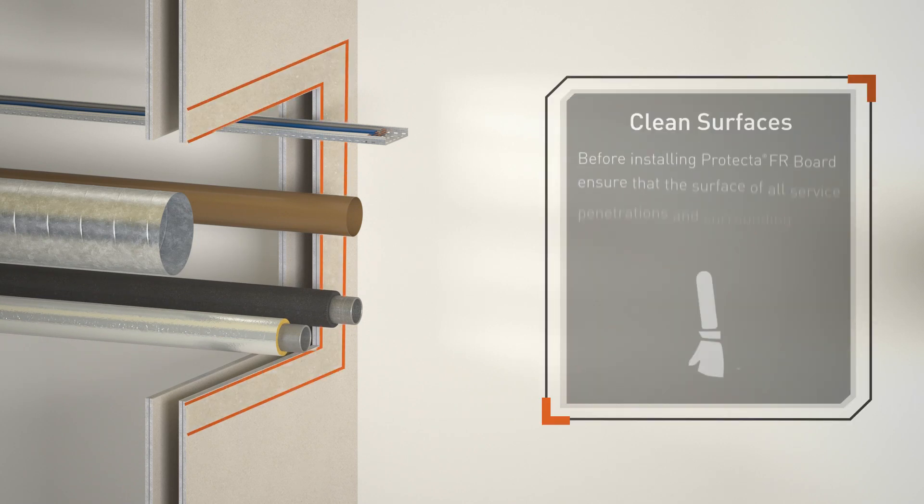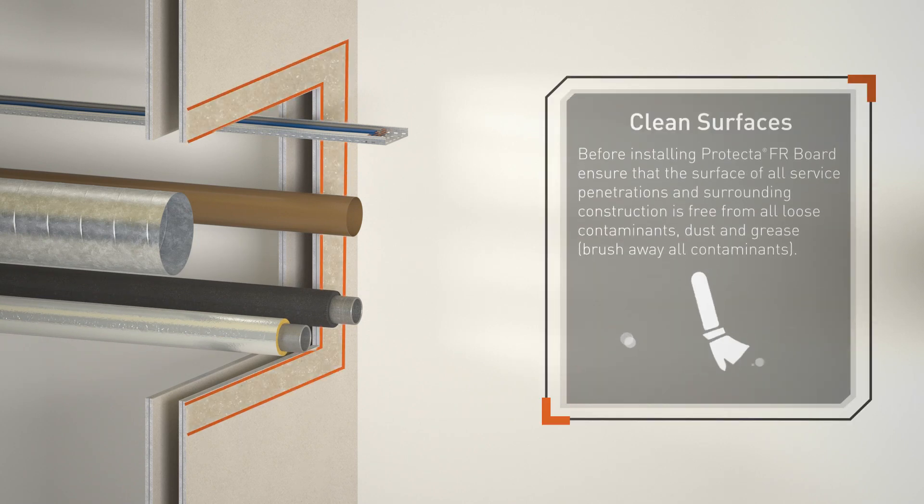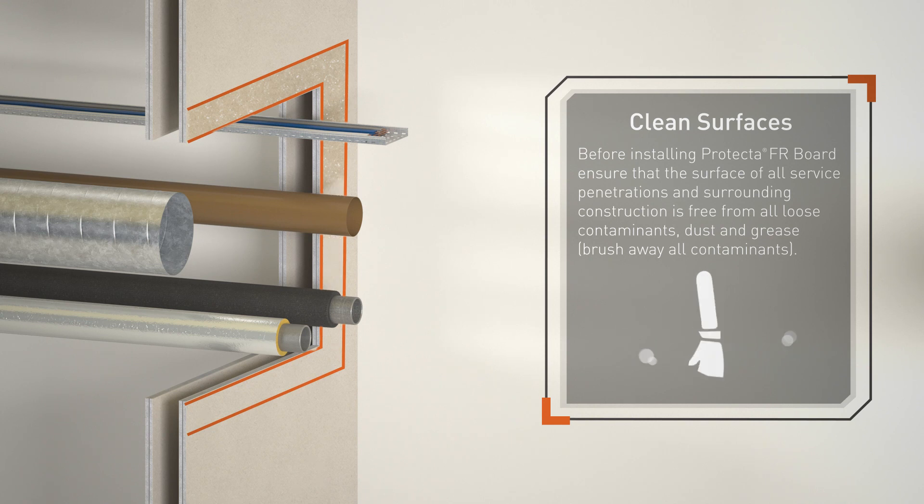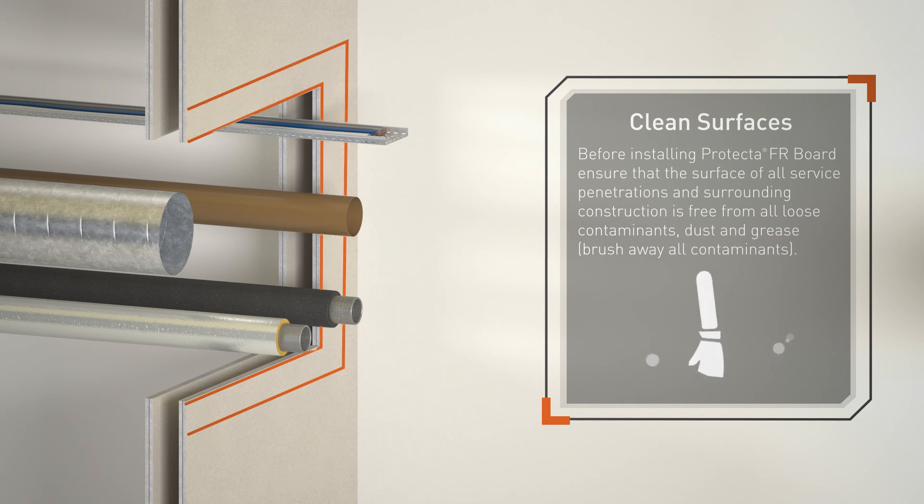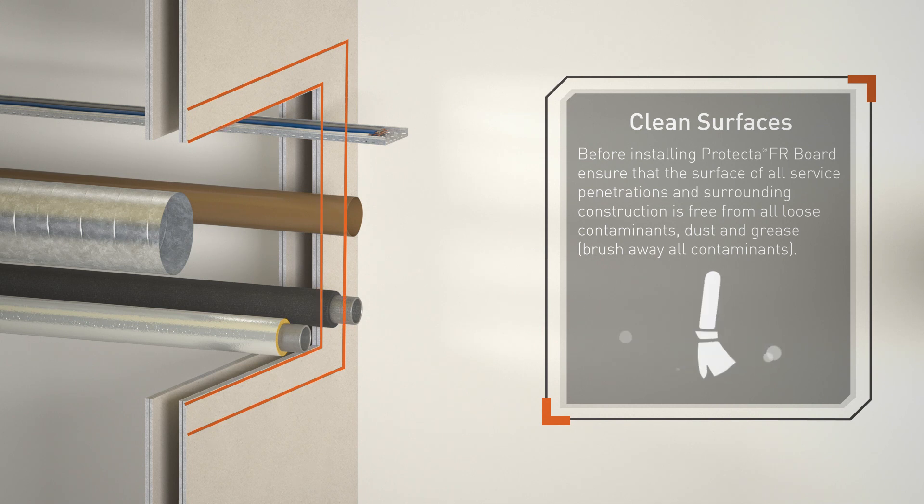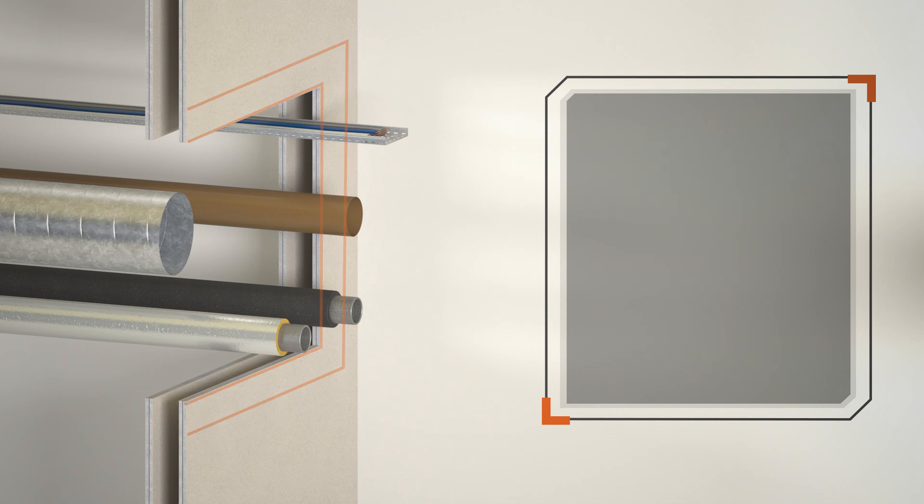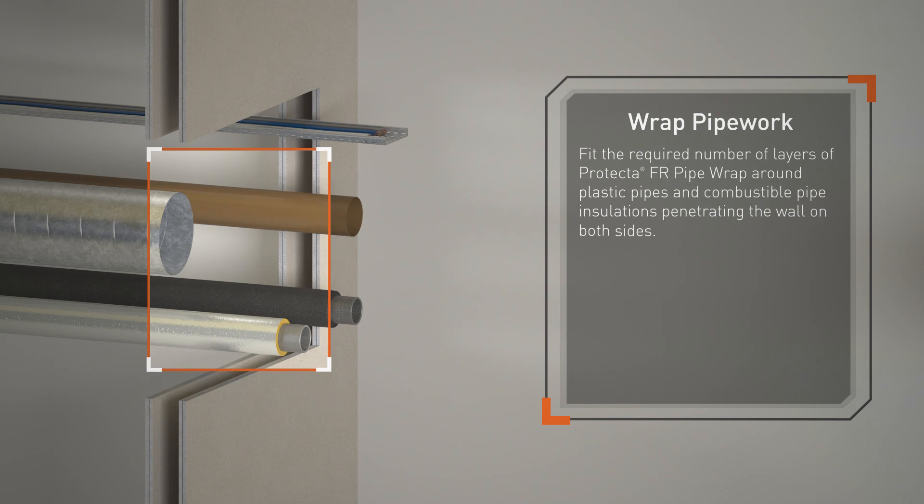Before installing Protecta FR Board, ensure that the surface of all service penetrations and surrounding construction is free from all loose contaminants, dust, and grease. Brush away all contaminants. Fit the required number of layers of Protecta FR Pipe Wrap around plastic pipes and combustible pipe insulations penetrating the wall on both sides.